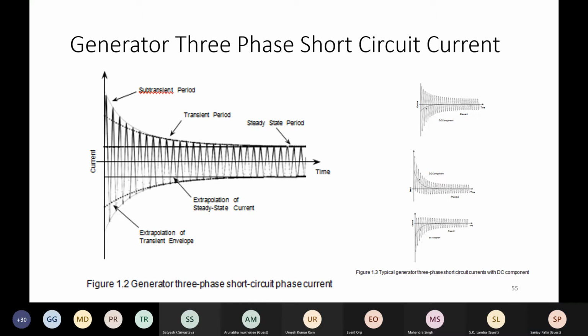The generator has a capability in terms of its ability to supply short circuit current. You are all aware that a generator has sub-transient, transient and steady state operation. When you say 40 kiloamp short circuit current, it is a steady state level. So the short time rating of all your equipment will depend on the steady state, which is a short time rating, 2-second rating, 3-second rating, or 5-second rating of the equipment.